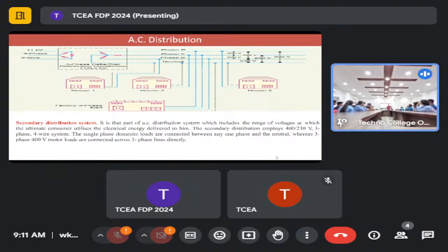Any transmission system must have an earth. Because otherwise, what will happen in the time of an earth fault? There will be no path. Any transmission system should be earthed. This is also transmission, but it is not called transmission, it is distribution. But in power transmission, and this part is delta, there is no neutral wire. Okay, this is the transformer. But the transformer is fed by a system which has earth.